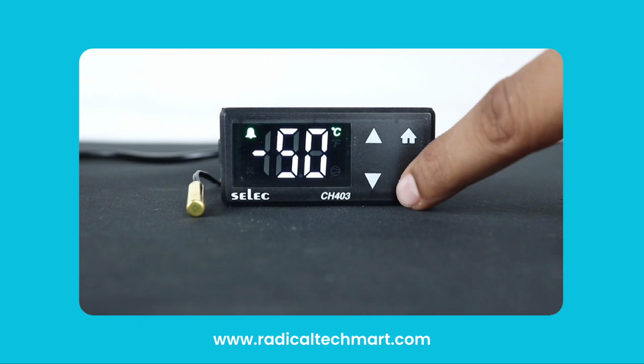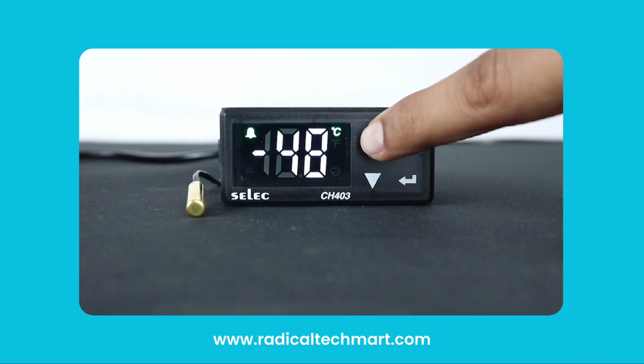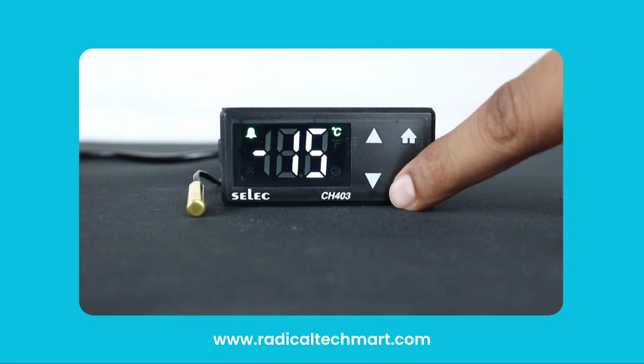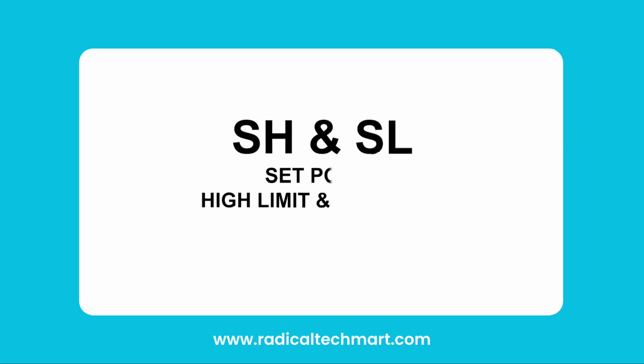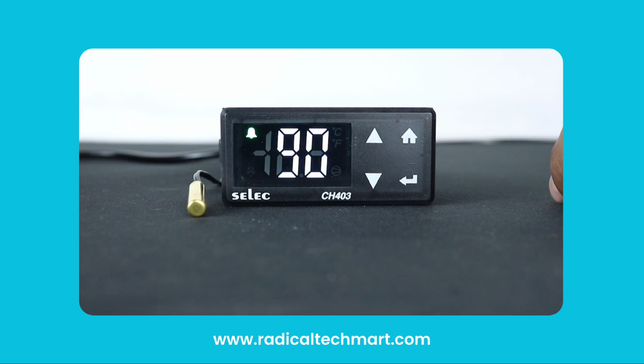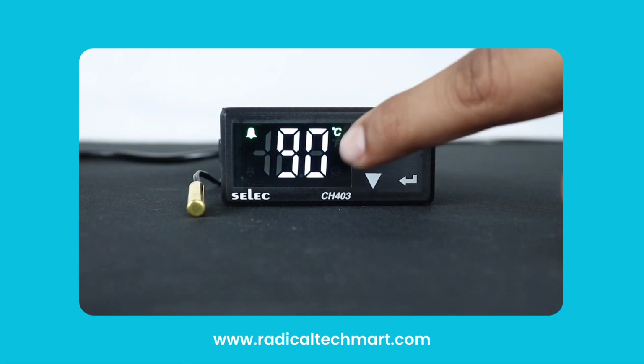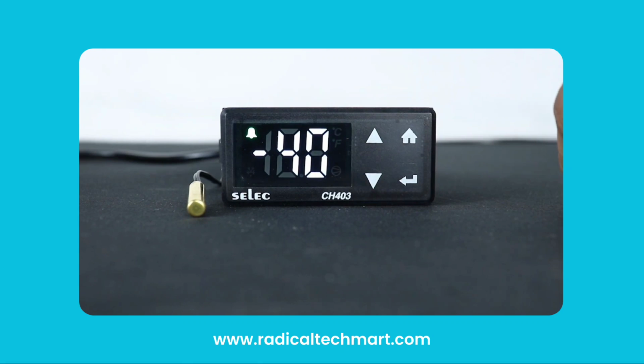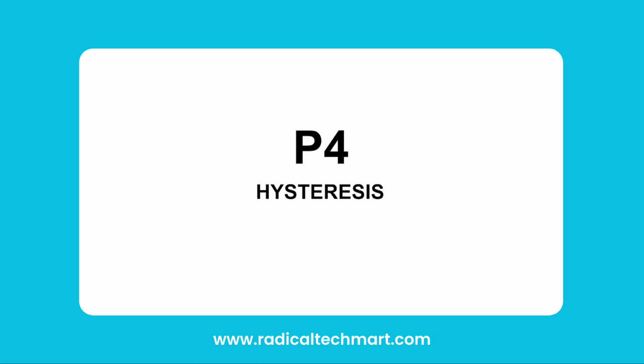The alarm bell symbol will glow when the present value reaches the high alarm or low alarm set values within the predefined range. The next parameters are SH and SL, which will limit the user to put the setpoint high range and setpoint low range respectively. P4 implies the hysteresis parameter.